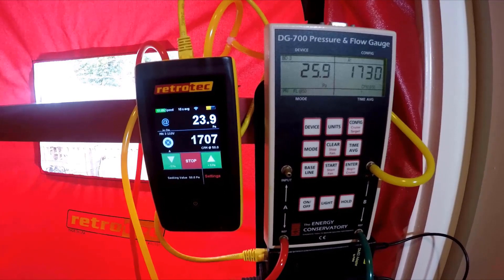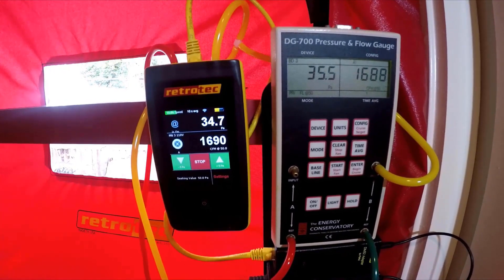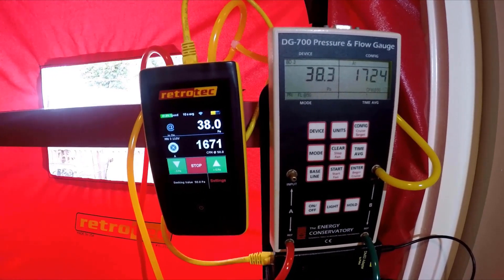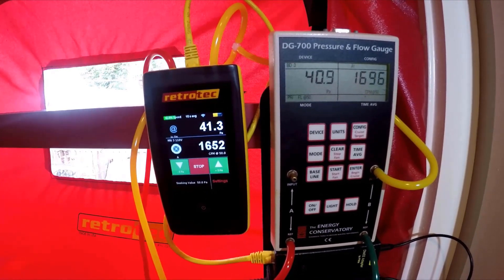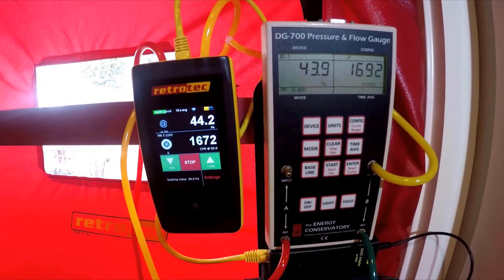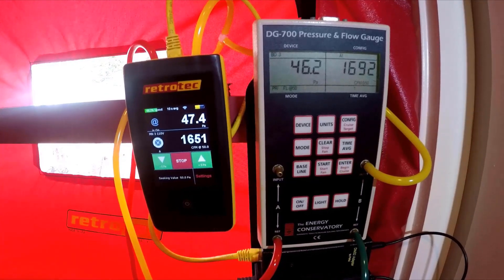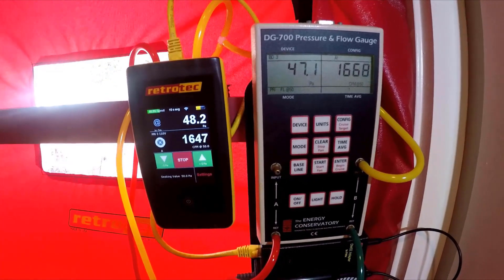So as we're ramping up our pressure we can see that these numbers are starting to align a lot better than they were last time. It's not perfect. The gauges will vary a little bit. Plus this DG700 is a little bit past its calibration date but working well enough to show how important it is to add this tube on to this port on this gauge when you're pressurizing a building.